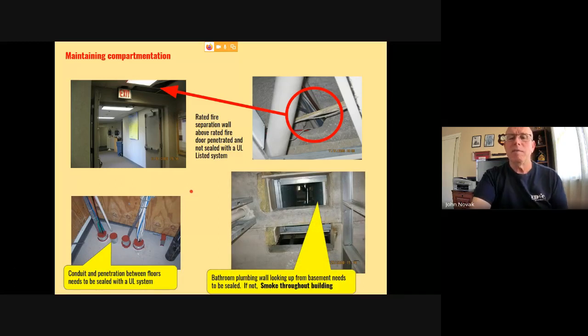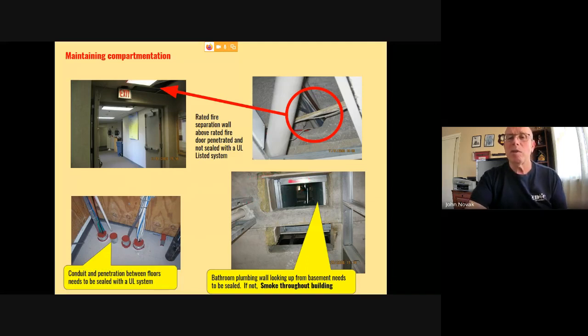So here's a picture of a building where it was still under construction, but we're looking up through the plumbing wall behind the bathtubs. So we're actually standing in the basement, and we can look all the way up to the top floor. So again, this was pointed out to the building inspector to make sure that on his final inspections all these were sealed up. So again, there's another area of fire spread, smoke spread throughout the building. If you had a fire in the basement or a fire in a bathroom, you have this open plumbing wall, smoke and flame could go up the plumbing wall to upper floors. And we'll see a case study of that in a few minutes.